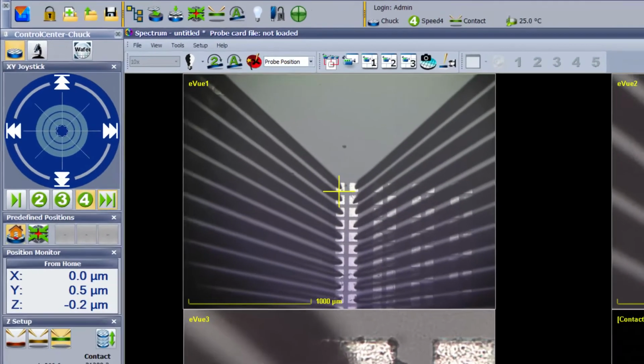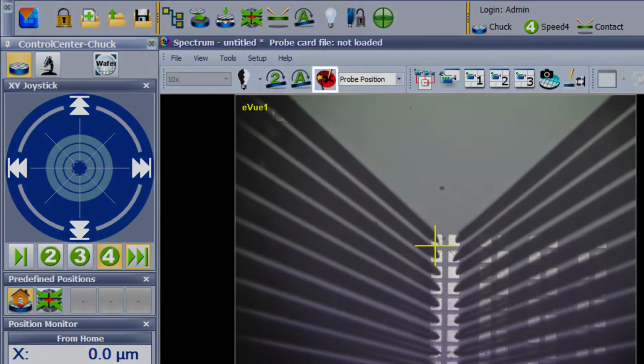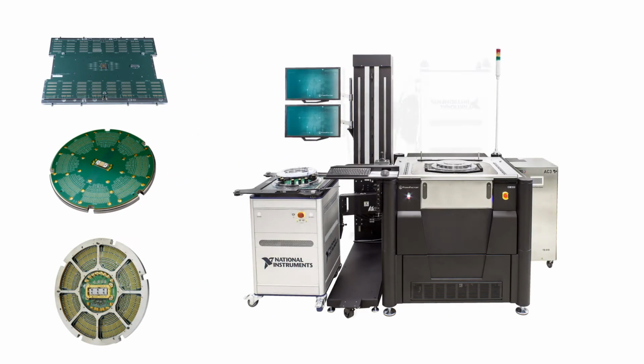ReAlign is an exclusive Velox feature that supports contact intelligence technology. It enables unattended testing over multiple temperatures for probe cards on the CM300XI by automatically aligning probe to pads. It is recommended especially for applications with limited microscope view, such as vertical and pyramid probe cards, or when using a test head.